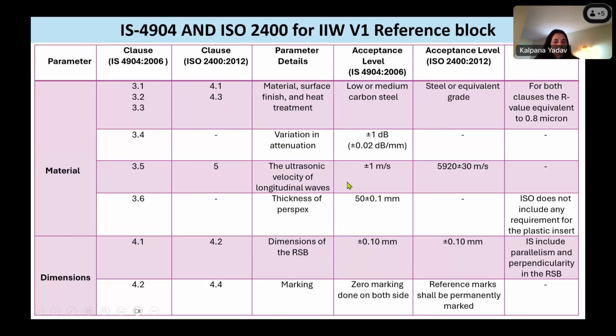The ultrasonic velocity is a major difference here. The acceptance level of the Indian standard is plus or minus 1 meter per second, but the acceptance level for ISO is plus or minus 30 meters per second. The thickness and the other requirements are the same, other than the ultrasonic attenuation and velocity measurement. For both, the surface roughness is equivalent to 0.8 micron. ISO doesn't include any requirement for parallelism, and IS includes parallelism and perpendicularity, which are not included in the international one. So, how parallel your reference block is going to be, and how the grains are aligned perpendicularly, is also included in the Indian standard.